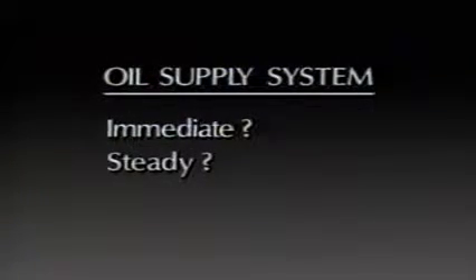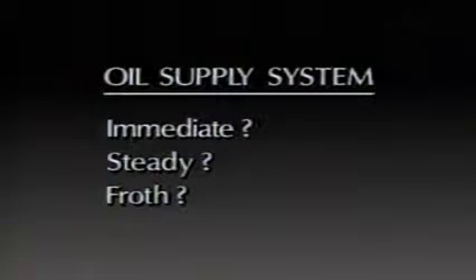Third, the ignition system. Do you hear the ignition arc buzzing? If not, tilt the transformer back and look for the arc as the springs disengage the electrode rods. Fourth, the oil supply system. Monitor it and see if the supply is immediate. Is it steady? Is there any froth indicating air in the supply system? No oil means a restriction or a severe air leak.